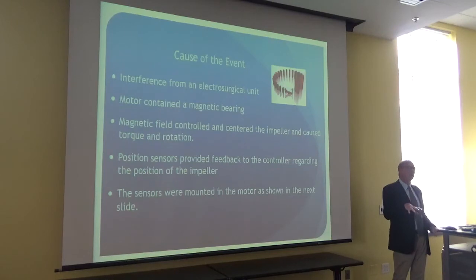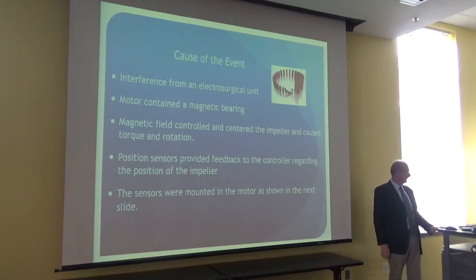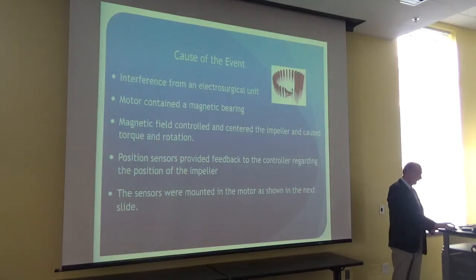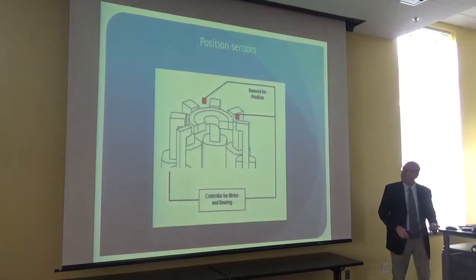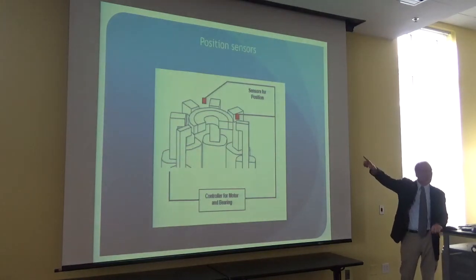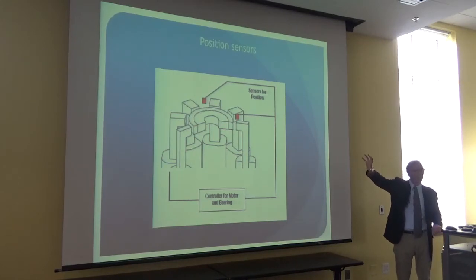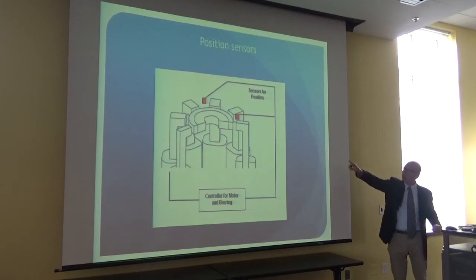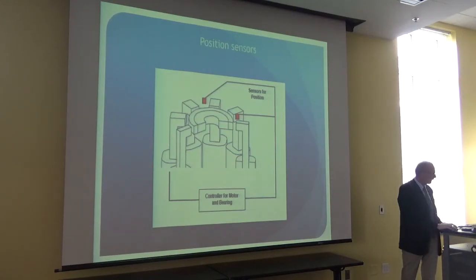We had position sensors in our motor that were sensing what the position of the impeller was. And they were actually mounted just like this. So we had 8 poles. We had little eddy current sensors in there. And as the impeller was rotating, we could actually use software to sense where they were and then control the position of the device, of the impeller.